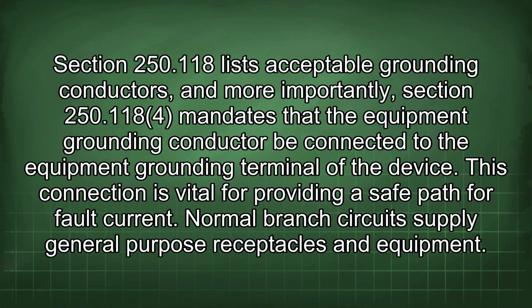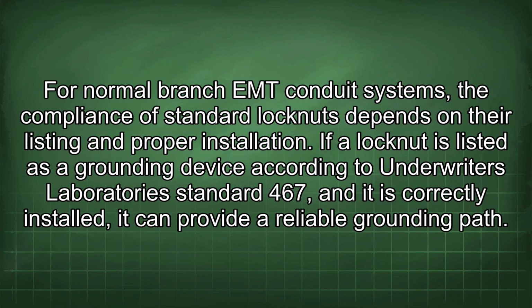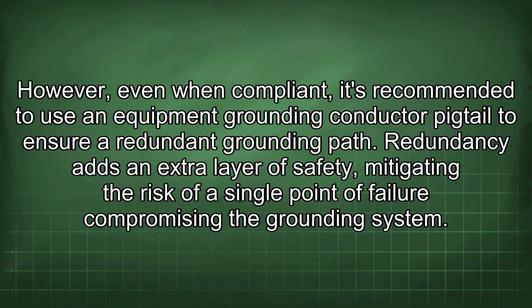Normal branch circuits supply general-purpose receptacles and equipment. For normal branch EMT conduit systems, the compliance of standard locknuts depends on their listing and proper installation. If a locknut is listed as a grounding device according to Underwriters Laboratory Standard 467, and it is correctly installed, it can provide a reliable grounding path. However, even when compliant, it's recommended to use an equipment grounding conductor pigtail to ensure a redundant grounding path. Redundancy adds an extra layer of safety, mitigating the risk of a single point of failure compromising the grounding system.